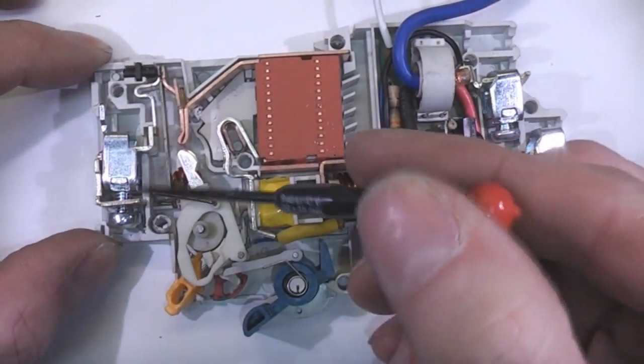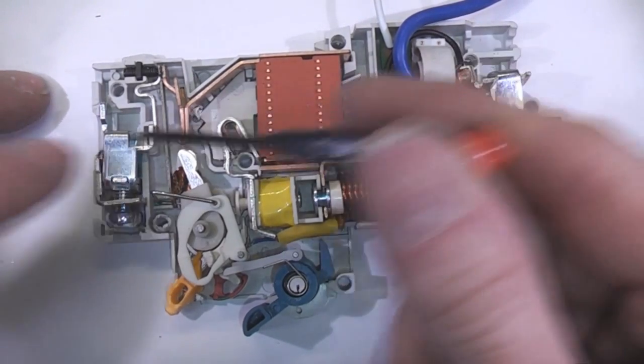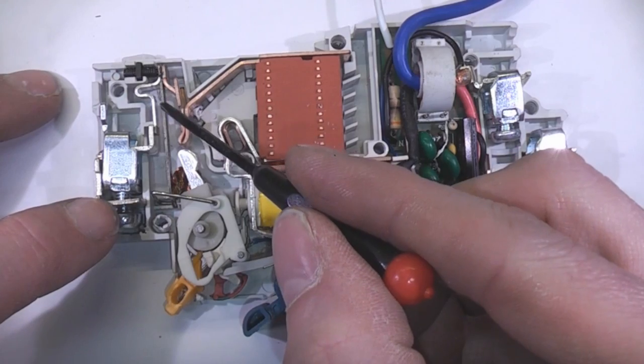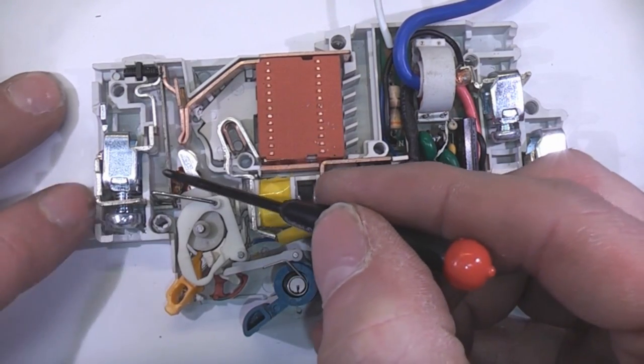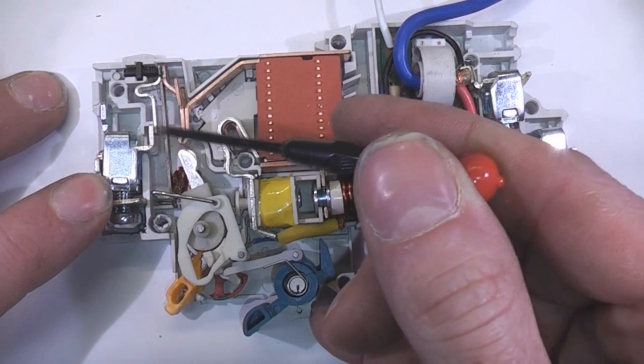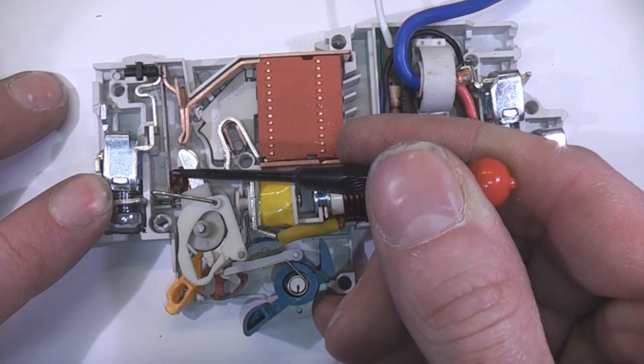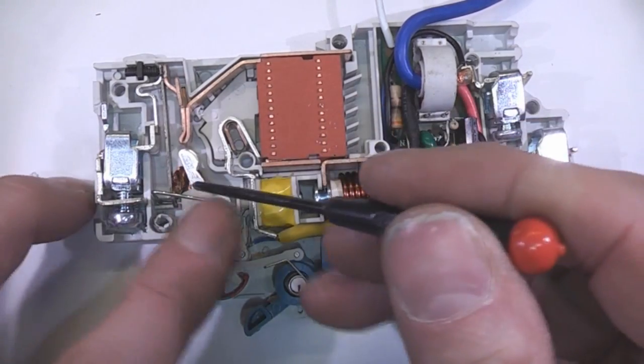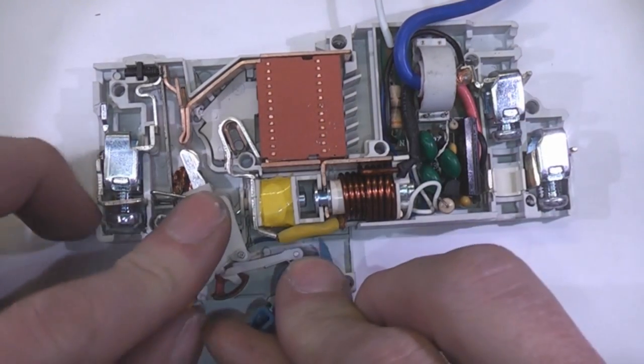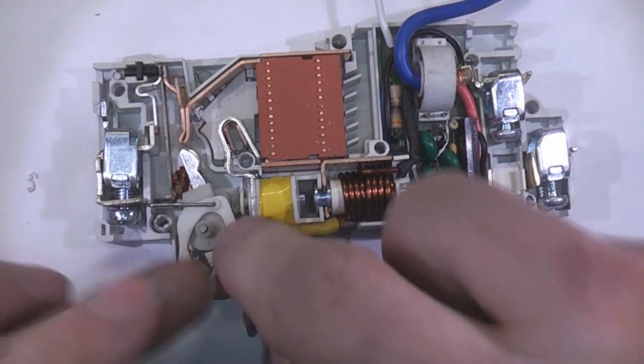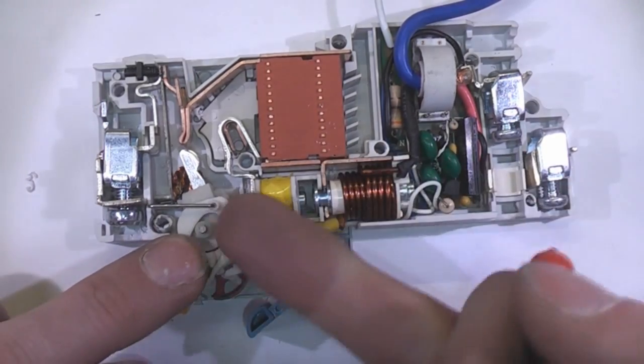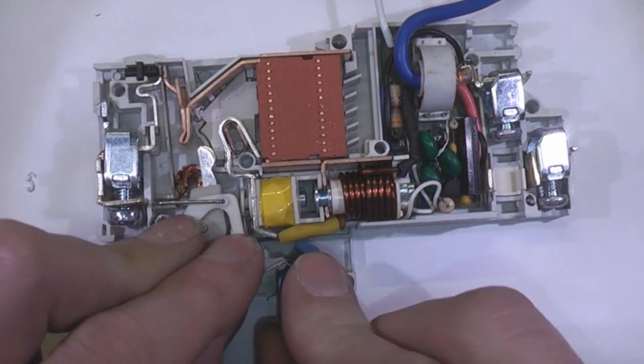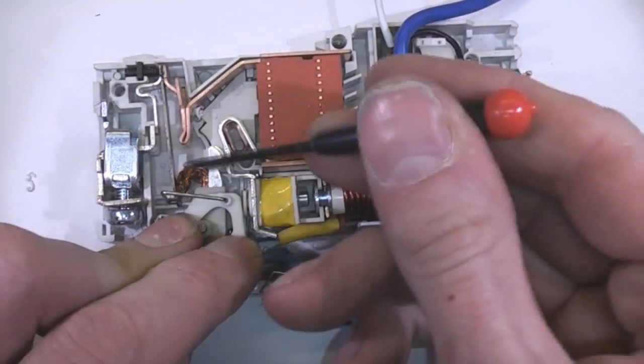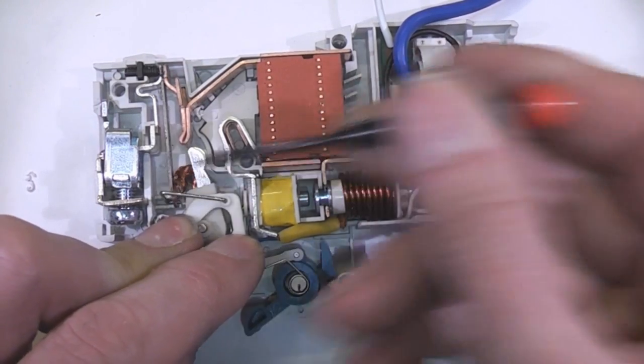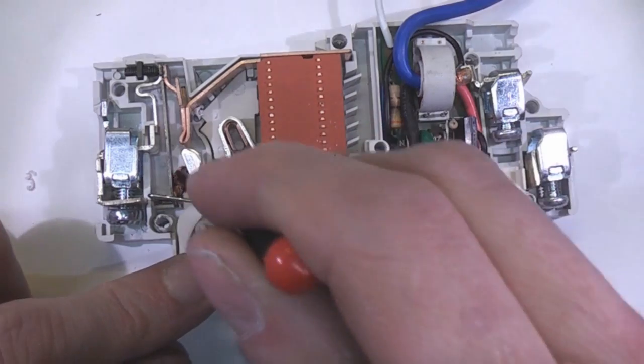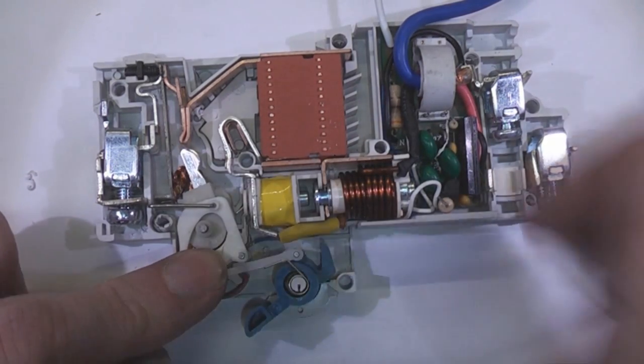And the overcurrent side of things, so we've got the live comes in here. The first thing that happens is it goes through this bimetallic strip. So this is the thermal protection. As the current increases, this will start heating up and it will start to bend in this direction until it pulls this lever. If I just reset this, it's a bit hard to hold it set because I haven't got the top cover on, and some of these shafts actually lock into the other side of the cover. But if we just set that, what will happen is, this heats up to the point where it pulls this and releases it. It then goes through this flexible wire to here.